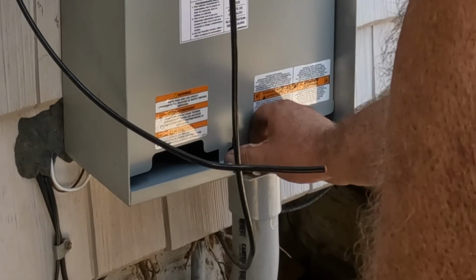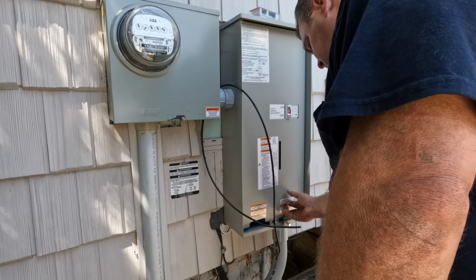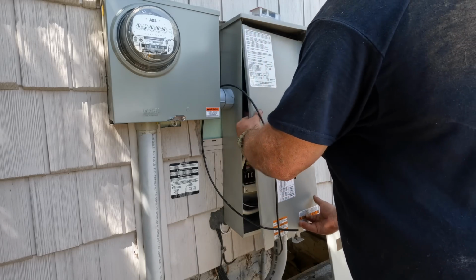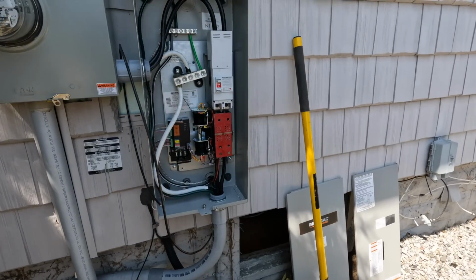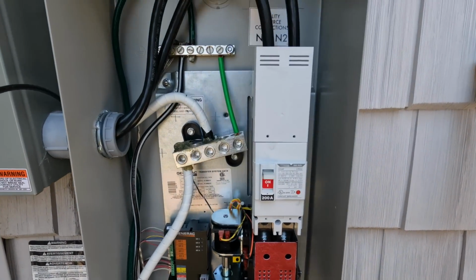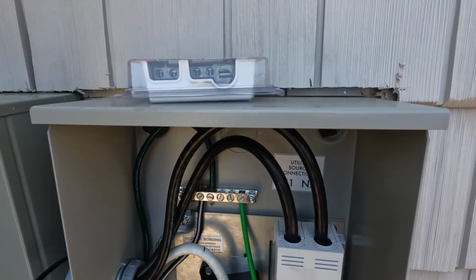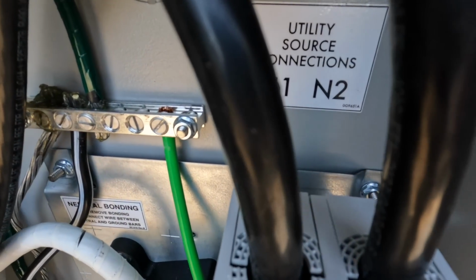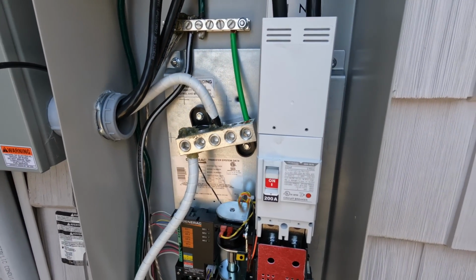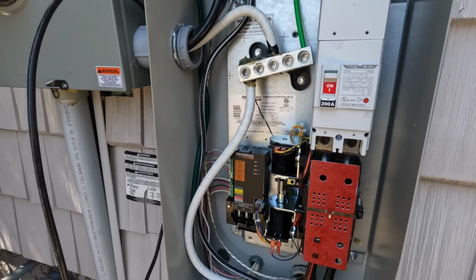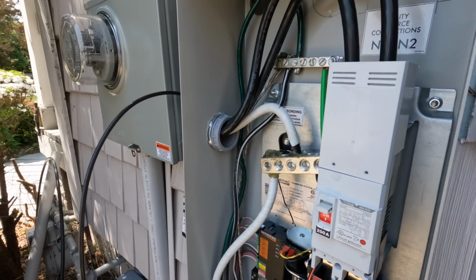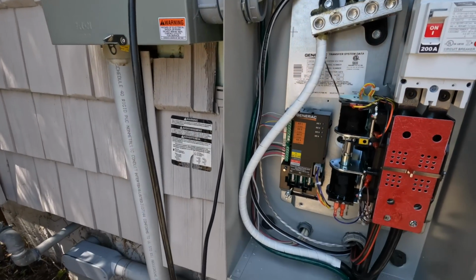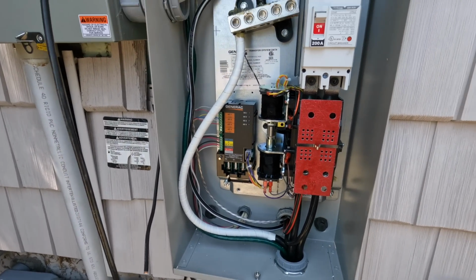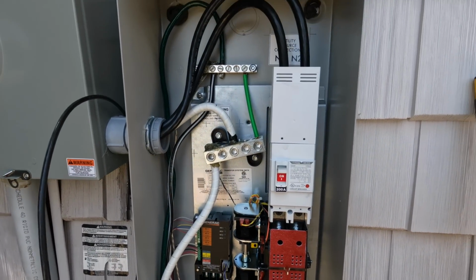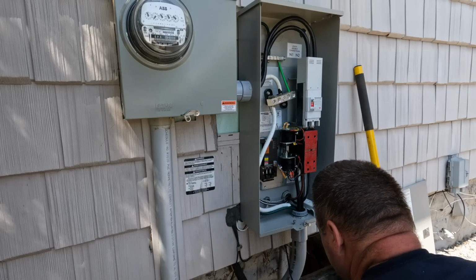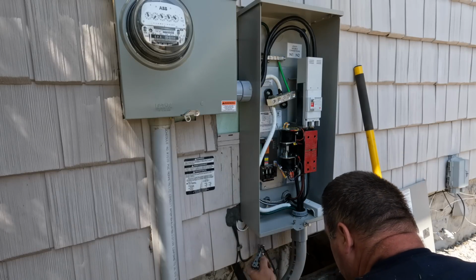Obviously, this is the main disconnect, so all your grounding electrode conductors go here, including the 2 ground rods that you see me hooking up. Okay, this is the wiring that I did. Up here, that's my line from the load side of the meter coming into the line side of the transfer switch. All your grounding and bonding and your main bonding jumper, which is that green wire up at the top there, gets done inside the main disconnect, and this automatic transfer switch is service rated and is the main disconnect for the whole house.